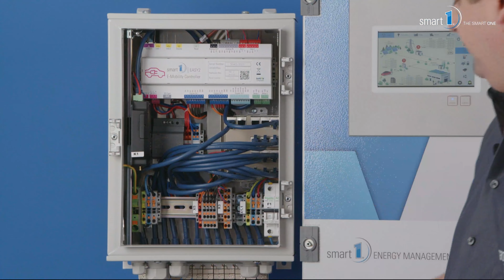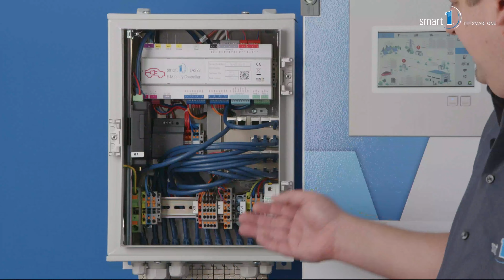And this is the reason why we have these Ethernet ports down here, so you can directly wire your charging stations to the box. You have keystone modules down here that you can take off. You can just have your installation wires coming to the box. You can attach it here, and then this is the solution for Ethernet. You would also install the meter directly into the system, so the meter is connected also directly to that box. Usually you do, since it's a close proximity in this solution, because everything is built inside the transformer station, usually you just take a wire from the meter Ethernet cable and attach it directly to the switch of the box that is built in, the 16-port switch.